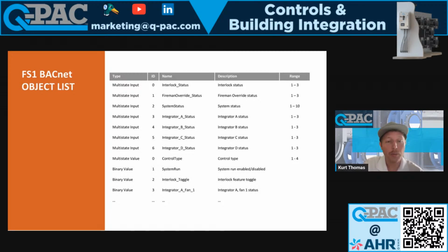The control type. So like we talked about earlier, control types are 0 to 10, constant static, constant CFM, or BACnet. So that'll tell you what control type you're in, and you can even dictate it there via BACnet if you would like. And then the binary values. So system runs, you can enable, disable the system via BACnet. There's an interlock toggle, and then binary value 3, 4, and on tells you what the status is of that particular fan. So we do give you individual fan status, and you can see the dots down below. That goes integrator A fan 1, integrator fan 2, all the way down to 9, and then it'll go down to integrator B fan 1, fan 2, and so on. So that's where you can monitor individual fan status.